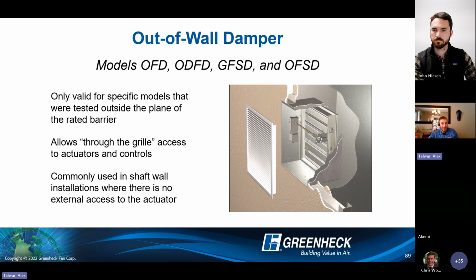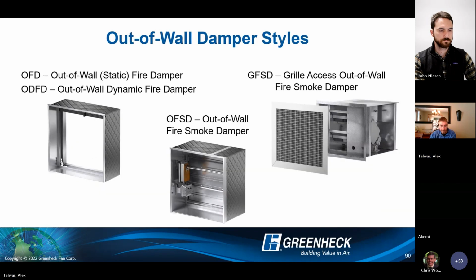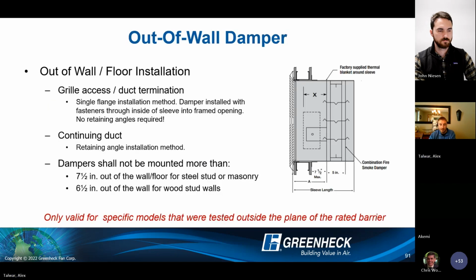So this is the out-of-wall products. So ODFD, OFSD, GFSD actually has a little grill compartment with a side actuator thing. I don't know how popular those are, to be honest, but the OFSD certainly is a popular one if you do need to offset the damper from the plane of the rated construction. All right, good summary slide here on the different out-of-wall product types that we have. So the curtain style products, the fire smoke damper, and then that kind of oddball grill compartment one as well.